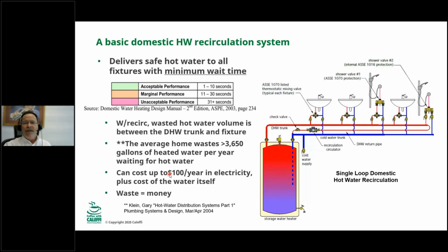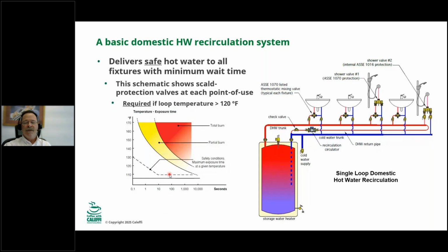Another point in that first sentence is to deliver safe hot water to all the fixtures. When we're talking about safety, the number 1 point to talk about is temperature. So again, this schematic shows anti-scald valves or point of use valves at every fixture. And if we're going to run this recirculation loop at any temperature above 120, we need to have anti-scald protection. And you can see in this graph here on the left that 120 degrees, if you come straight across, it's pretty safe. It's considered safe because most people can get out of the way of that 120 degree water, and it won't scald you for a few minutes. So generally that's considered safe. But if we're going to run temperatures higher than that, 130 or 140, that's when we have to have anti-scald valves.